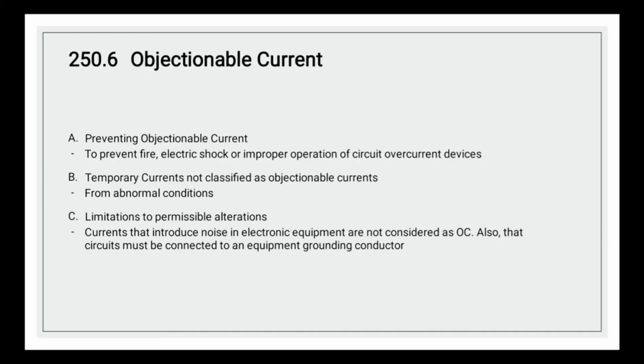Okay, we continue in Article 250 with section 250.6 about objectionable current. This section is about how to prevent objectionable current, temporary current not classified as objectionable current, and the limitation to permissible alterations. Why do we have to prevent objectionable current? Because we want to avoid fire, electric shock, or improper operation of circuit overcurrent devices.